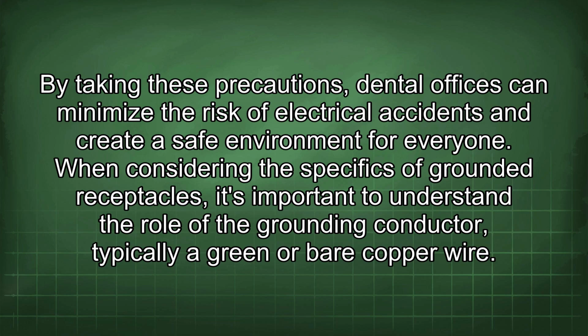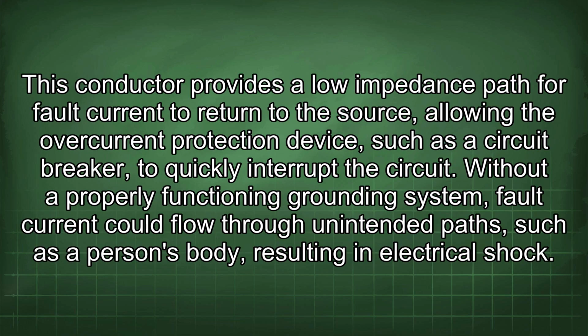When considering the specifics of grounded receptacles, it's important to understand the role of the grounding conductor, typically a green or bare copper wire. This conductor provides a low impedance path for fault current to return to the source, allowing the overcurrent protection device, such as a circuit breaker, to quickly interrupt the circuit.